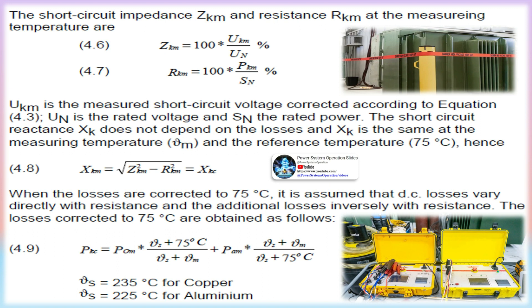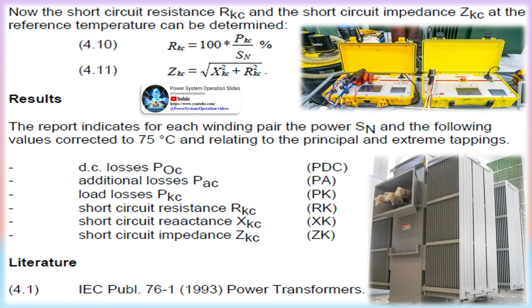IEEE lists standardized impedances for distribution class transformers above 500 kVA at 5.75% plus minus 7.5%, but sometimes customers will request something different. This can be largely accomplished with the design itself. The impedance percent IZ of a transformer is affected by the resistive percent IR and reactive percent IX components of a transformer. It is during this test that the reactive and resistive components of impedance are identified, as well as the resulting X by R ratio of a unit.